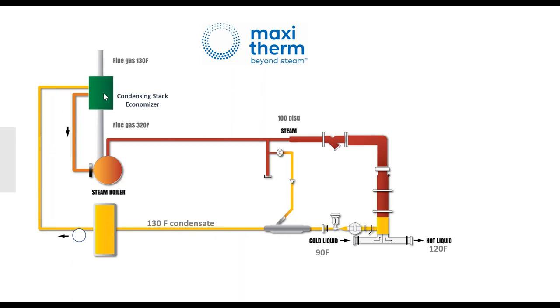If you had a condensing stack economizer, just like they did at Duke University, this becomes a condensing steam boiler: 90 plus percent efficiency, longer life than any condensing boiler on the market, much better turndown, O2 trim ratio, and all the things about a steam boiler.